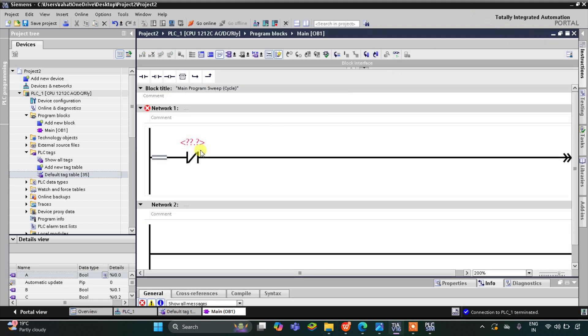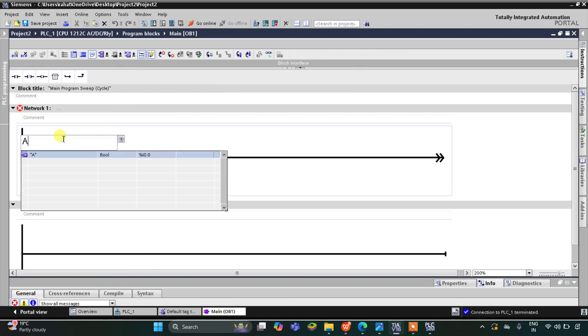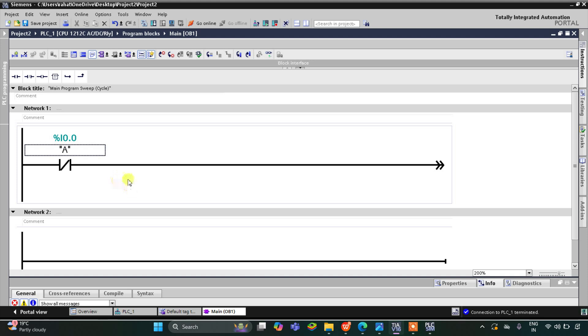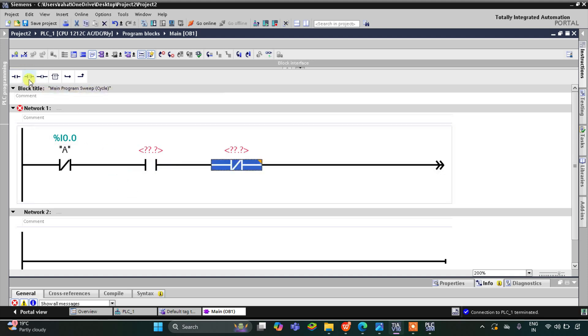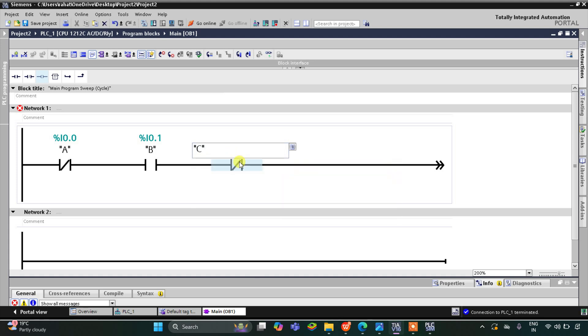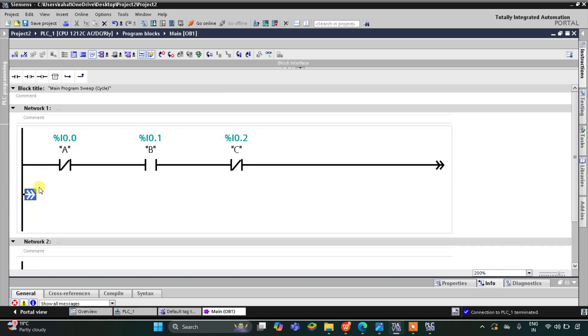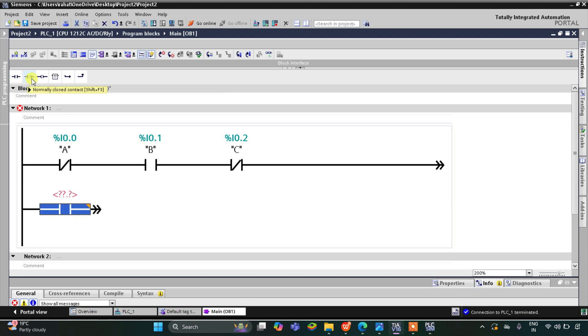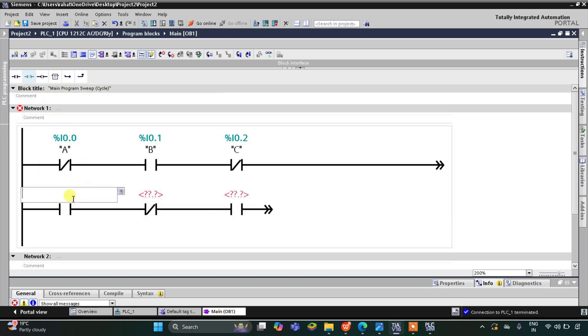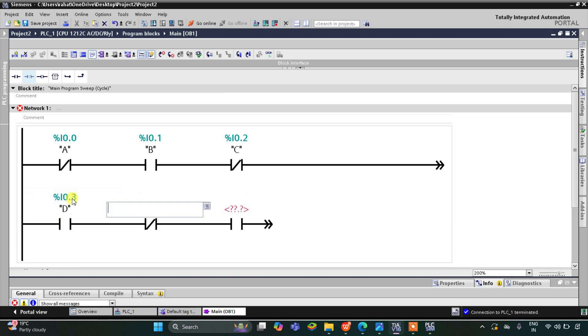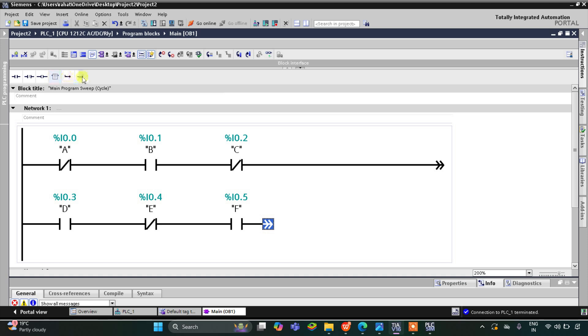Let's minimize this. This will be A because in the example it was A-naught, then B as a normally open contact and C as a normally closed contact. This represents B and this represents C-naught as a normally closed contact. Then plus means in parallel — OR logic gate. So I will open the branch. For D I will insert a normally open contact, for E a normally closed contact, and for F a normally open contact. This will be D, then E, then F. I will close the branch and then insert a coil for output Y.